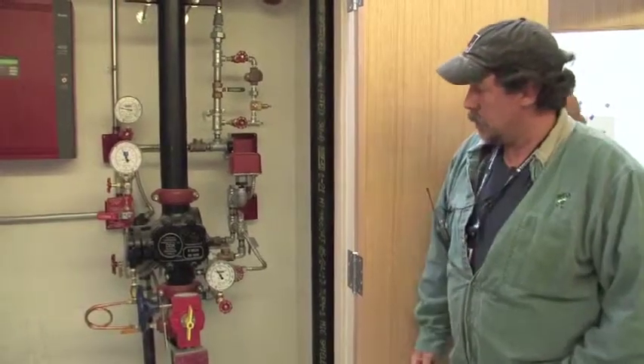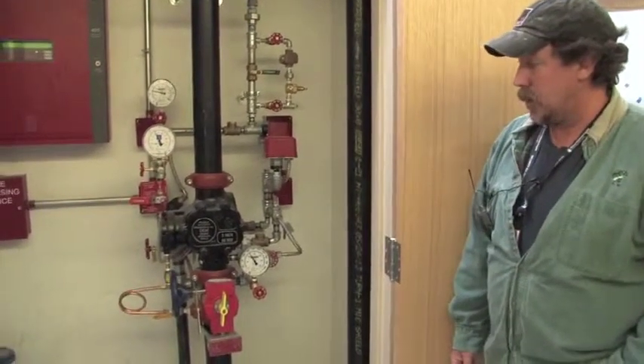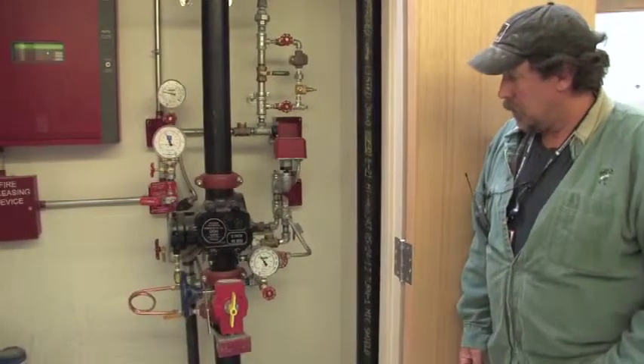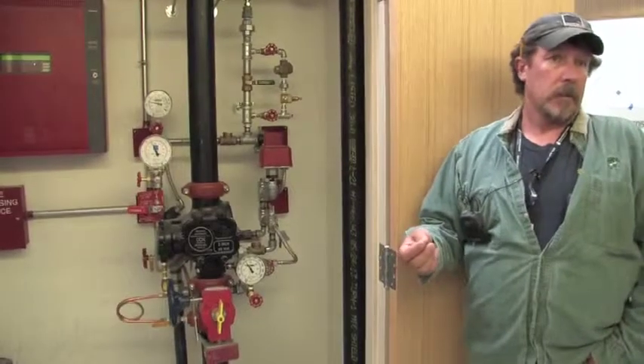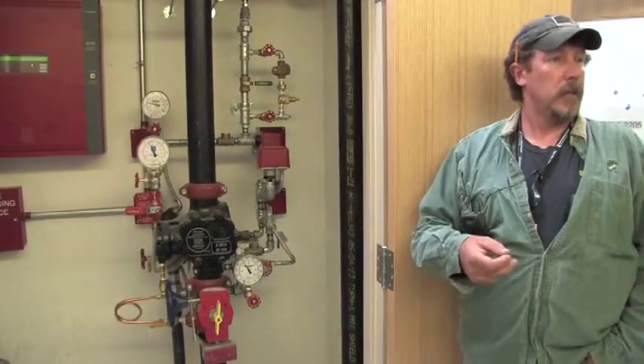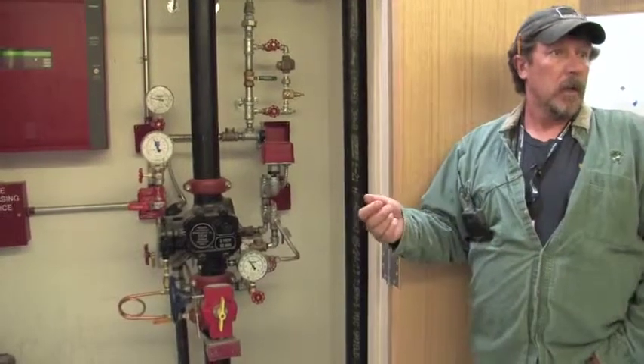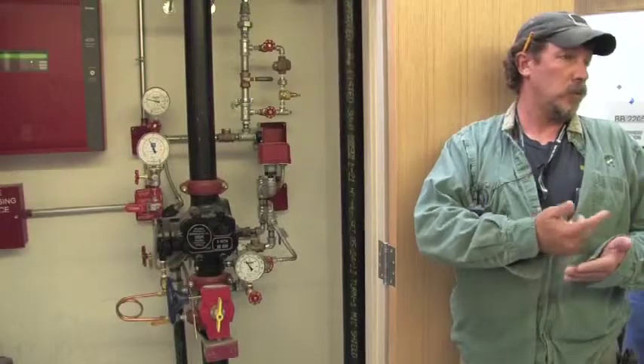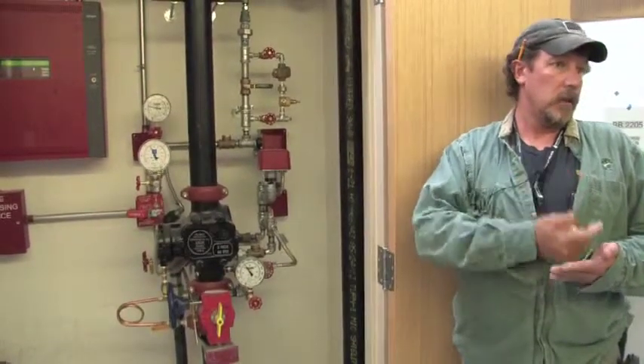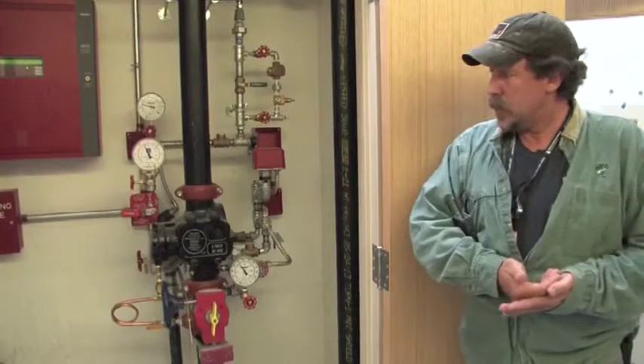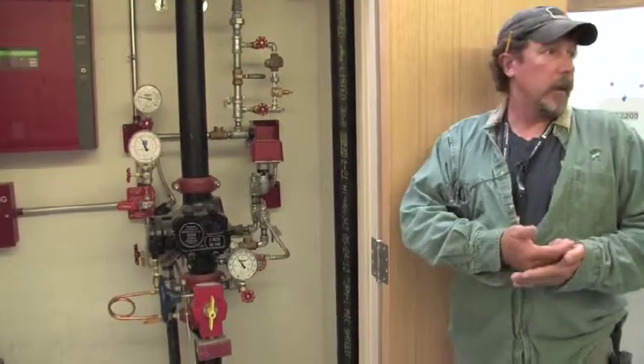And you see a basic DDX double interlock pre-action valve right here. Takes 2 things to set it off. As we all know, it takes a smoke detector or heat detector, probably is what they're using. So that's got to go off to activate the solenoid to trip the valve. But if the valve trips, you're only going to get water to a closed system, so you need 2 things to set off a pre-action system. You need it to electronically set off by that, and you also need a head to release so it'll fill with water and get out.